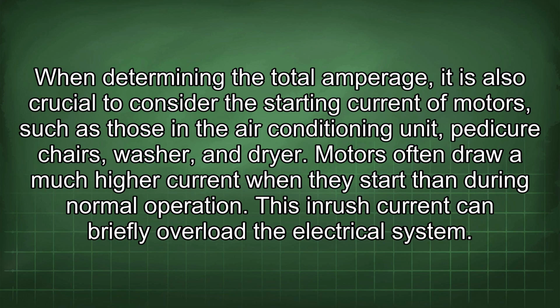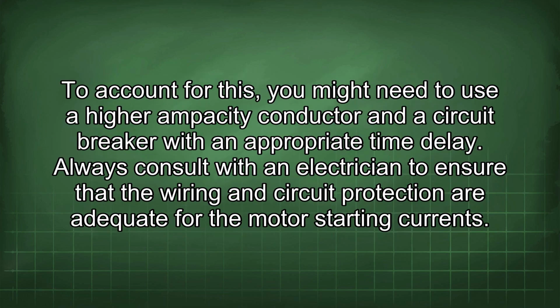When determining the total amperage, it is also crucial to consider the starting current of motors, such as those in the air conditioning unit, pedicure chairs, washer, and dryer. Motors often draw a much higher current when they start than during normal operation. This inrush current can briefly overload the electrical system. To account for this, you might need to use a higher ampacity conductor and a circuit breaker with an appropriate time delay. Always consult with an electrician to ensure that the wiring and circuit protection are adequate for the motor starting currents.